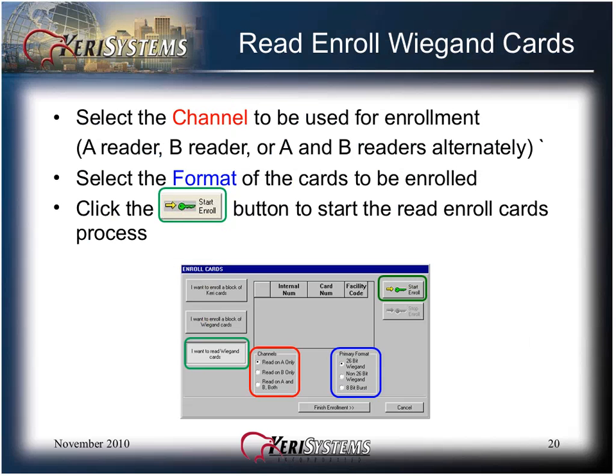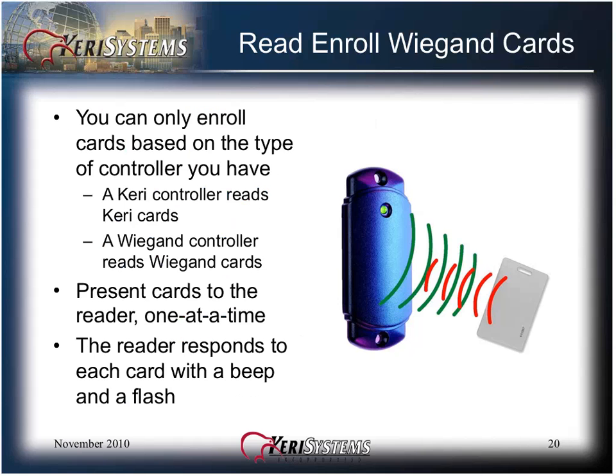If you are Read Enrolling Wiegand Cards, select the channel to be used for enrollment: the A Reader, the B Reader, or A and B Readers alternately. The A and B Readers refers to the connection point of the reader on the master controller. The A Reader is connected to Terminal Block 5; the B Reader is connected to Terminal Block 6. Select the format of the cards to be enrolled and then click the Start Enroll button. You can only enroll cards based on the type of controller you have — a Keri Controller reads Keri Cards, and a Wiegand Controller reads Wiegand Cards.